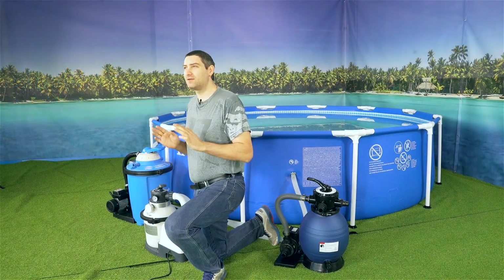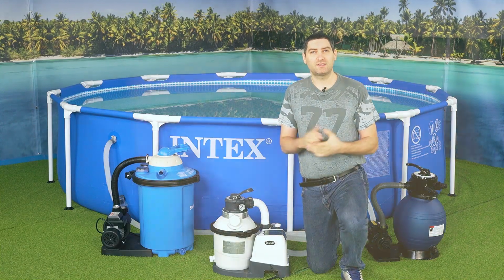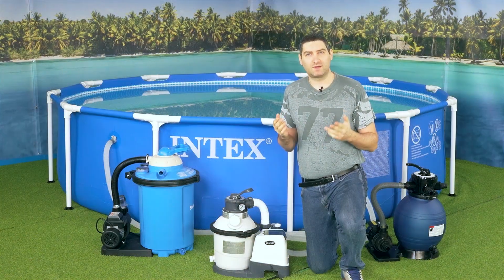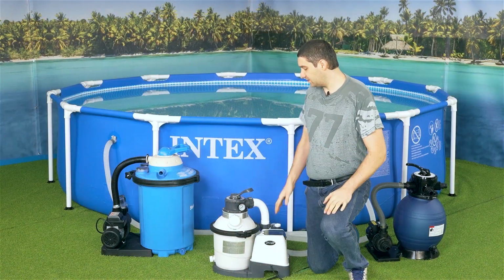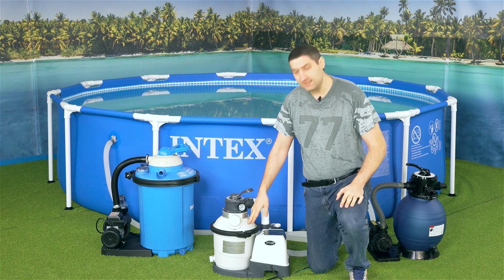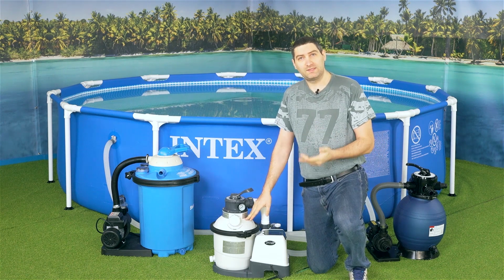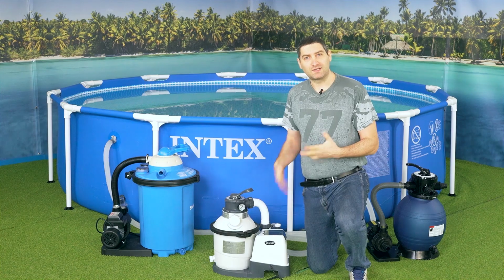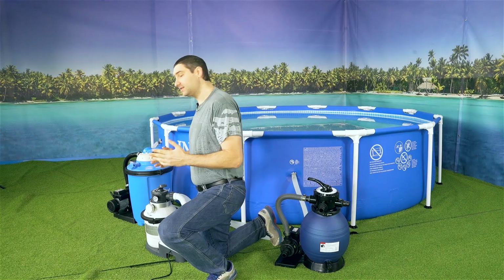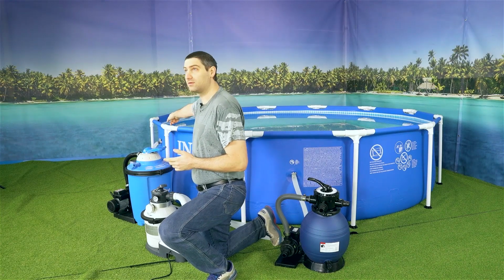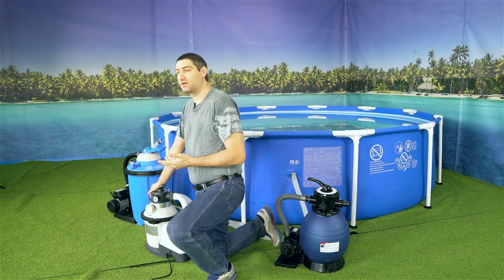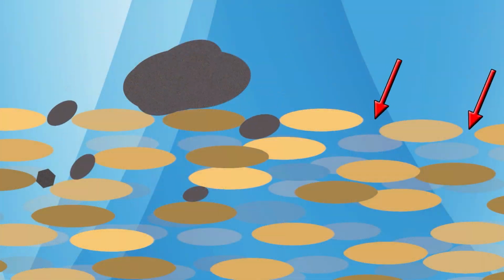Then we look at the filter media next. Sand is most commonly used. Here you have the advantage that sand is very cheap to buy. The water that comes from the pool goes into the sand filter system and is pressed through the sand here in the tank, and the coarse particles get stuck in the sand, and that is practically the filter process. Then the filtered water goes back from the sand filter into the pool, and that's pretty much the whole process. I just said that the coarse particles get stuck because the smaller particles, which are smaller than the grain of sand, simply rush through.